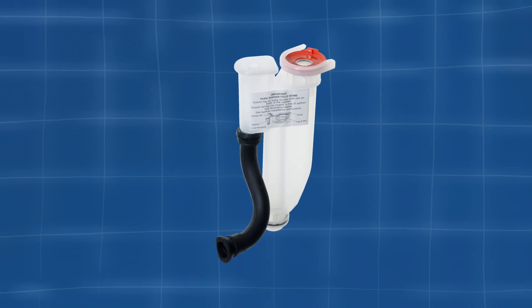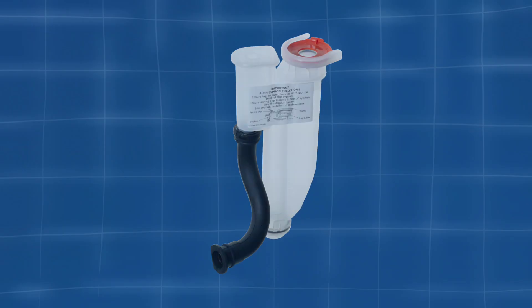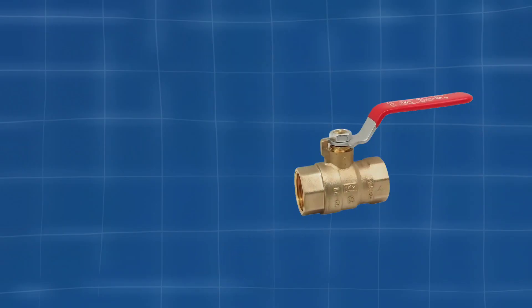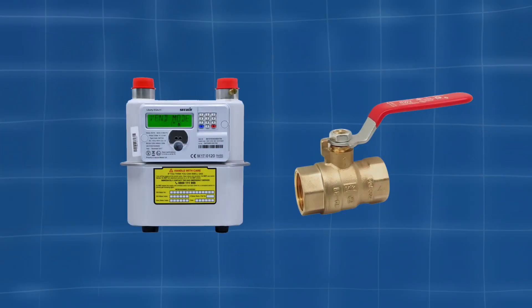A frozen or blocked condensate pipe, especially in winter. No gas supply. Maybe a closed valve, credit runout, or a network issue.